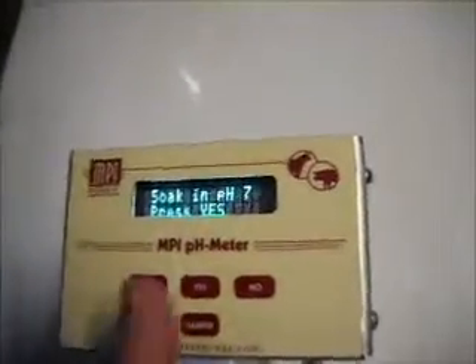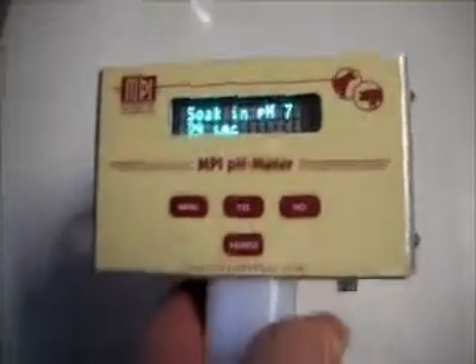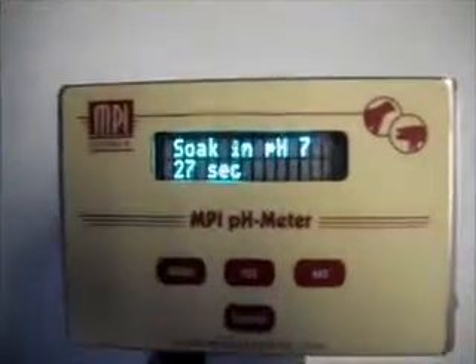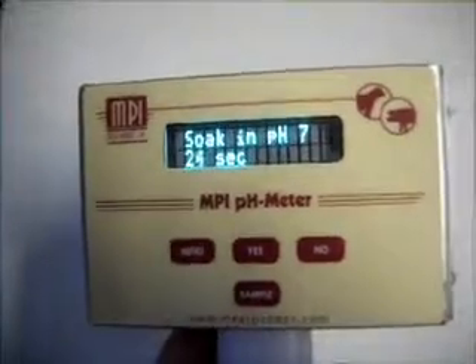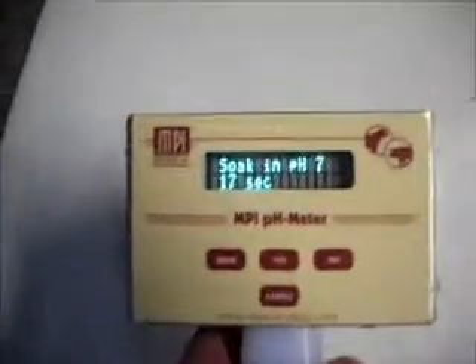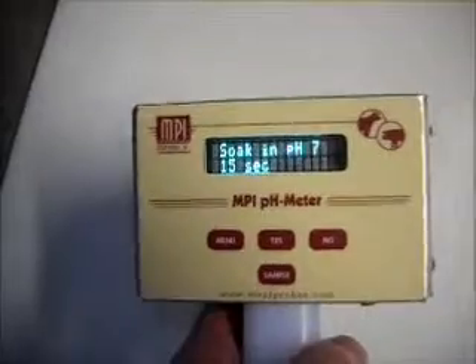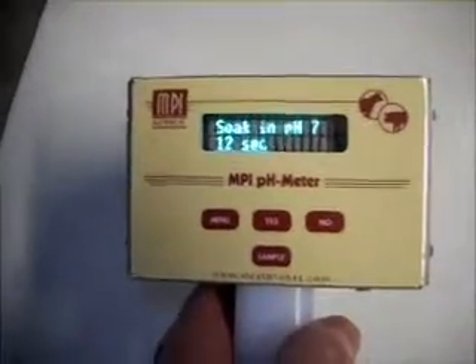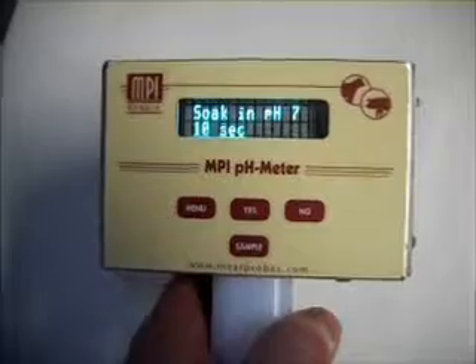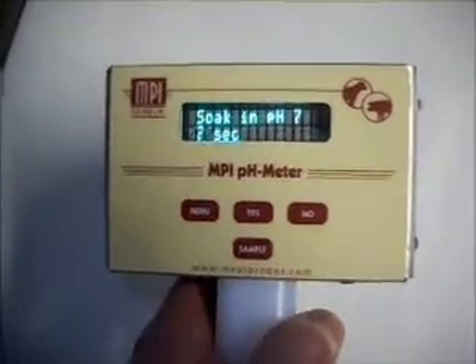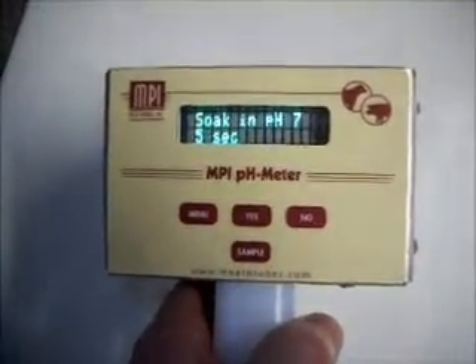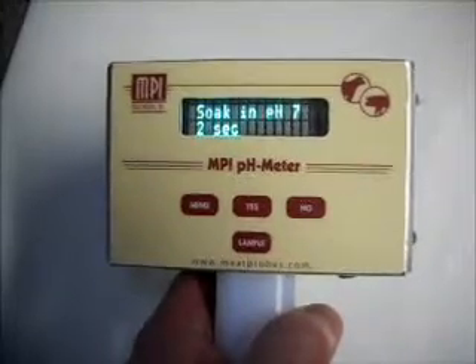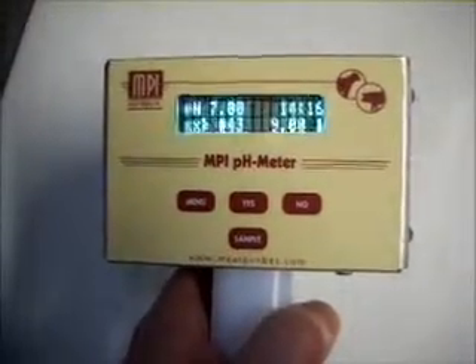So we're going to put that in the buffer there, and then after we have it immersed in the buffer, we're going to go ahead and start calibrating. Again, it takes about 30 seconds to get the calibration done in buffer 7. Again, we swish it a little bit so we can get a good solution. Wait for it to get done, and after that, it will ask us to go to the next step. So that's all there is to it.